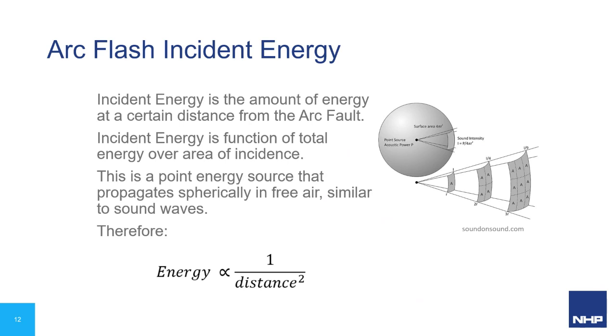There's a term that's used quite a lot called incident energy, so I just wanted to explain exactly where that incident energy comes from. Incident energy is basically the total energy over the area of incidence. Think of it like pressure or sound wave intensity. You've got a point source of energy that expands out in a spherical fashion, so it propagates in that spherical area. As you go out to further distances, it's a 1/distance-squared relationship, so that energy is being dissipated. It's an important relationship to keep in mind: the further away you get from the initial source of the energy, the far better off you are. It's proportional to 1/distance-squared, very important.